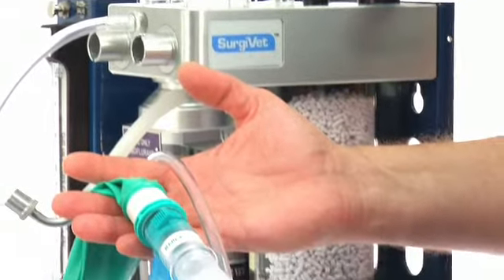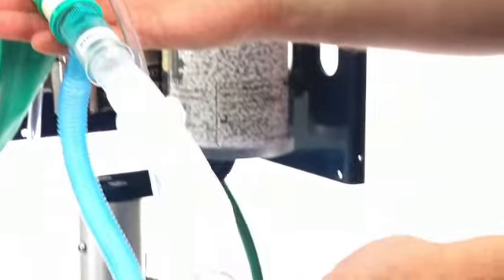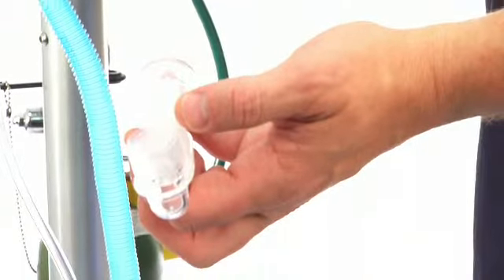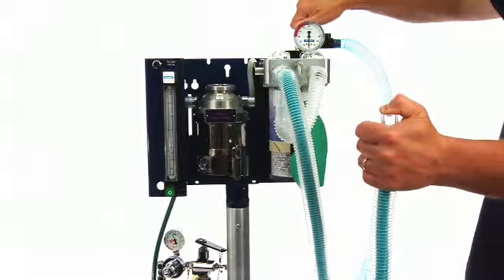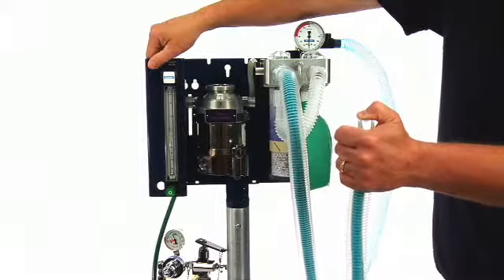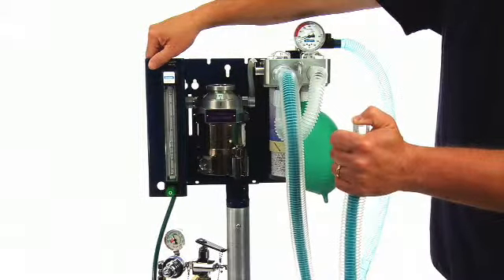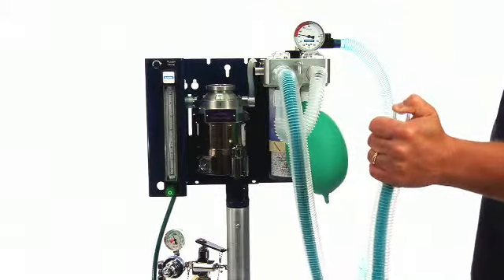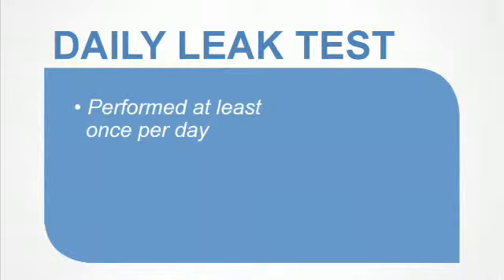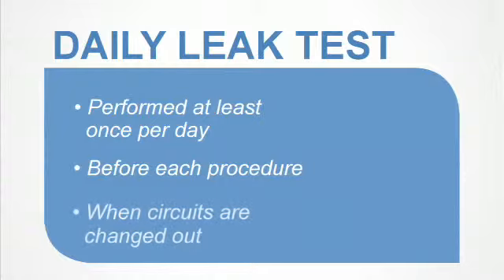The anesthesia machine should be evaluated daily, and inspection of parts should be performed. A pressure test is also recommended prior to each patient or whenever a component of the breathing system is changed. Daily machine leak test. The daily machine leak test is recommended to be performed at least once a day, ideally before each procedure or when circuits are changed out.